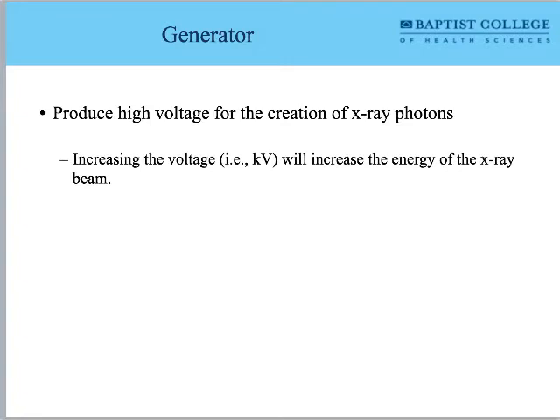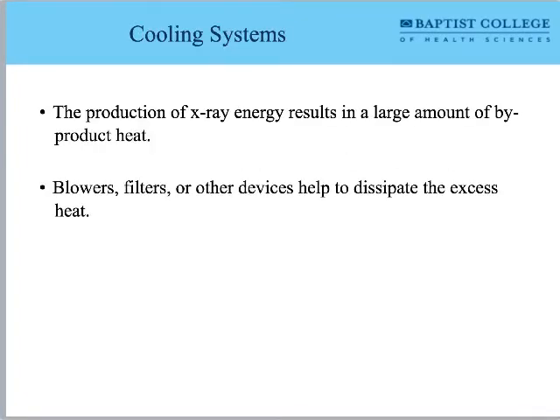We need a generator to provide high-voltage power for x-ray photons. We want to increase the voltage into the kilovolt range using transformers to increase the energy range of the x-ray beam into the diagnostic range — where the photoelectric interaction can occur. We need cooling systems because the x-ray tube is essentially a giant toaster: over 99% of what it produces is heat, so we have blowers, filters, and all sorts of devices to dissipate the excess heat. When you've done a few CT scans, that room gets hot.